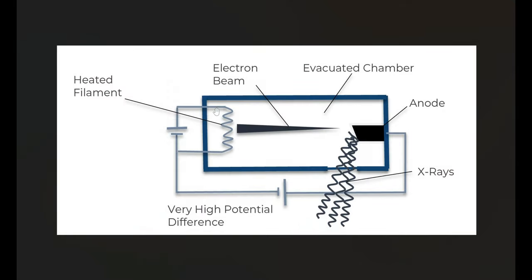In our x-ray tube, we have our filament. The heated filament is going to boil off electrons. When the electrons are created, if the filament is held at a negative charge and the anode on this side is held at a positive charge, the electrons will flow from the cathode towards the anode. Once they strike the anode, they will create x-rays. The interaction of the electrons with the anode will create two kinds of x-rays: bremsstrahlung x-rays and characteristic x-rays.